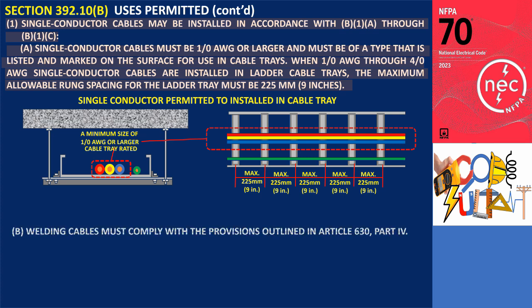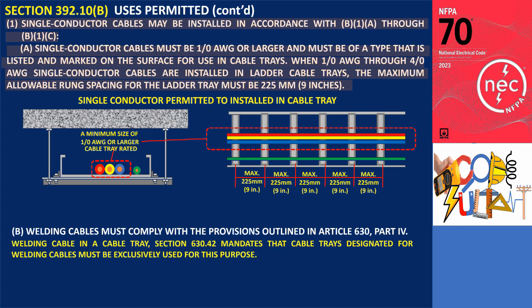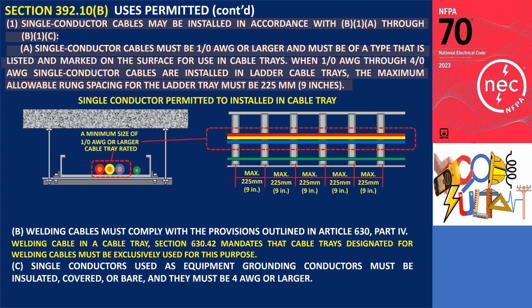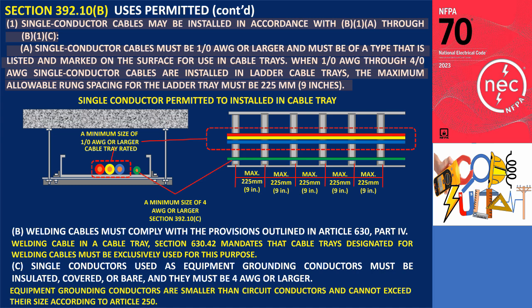Regarding welding cables under B.1(b), they must comply with the provisions outlined in Article 630, Part 4. Section 630.42 mandates that cable trays designated for welding cables must be exclusively used for that purpose. Under B.1(c), single conductors used as equipment grounding conductors must be insulated, covered, or bare, and must be 4 AWG or larger. Since equipment grounding conductors cannot exceed the size of circuit conductors per Article 250, this section permits a minimum size of 4 AWG to be installed in the cable tray.